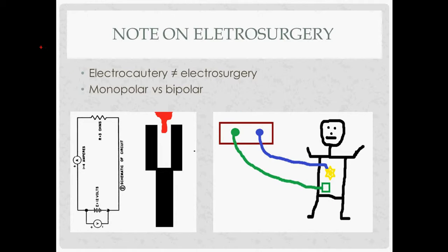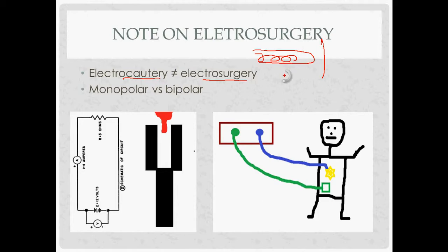Electrosurgery and electrocautery are actually a little different. Electrocautery is when you have a tool with an electrode inside that heats it up, and you touch the hot surface to whatever you're cutting or coagulating — it basically burns it. Whereas with electrosurgery, you have an electrode that transmits electricity outside of it, and the electricity transmitted is what does the actual cutting or coagulating.